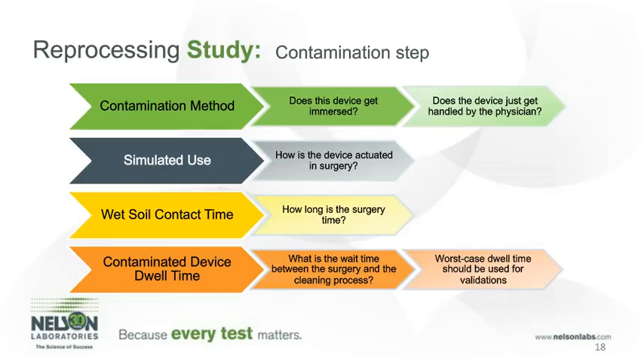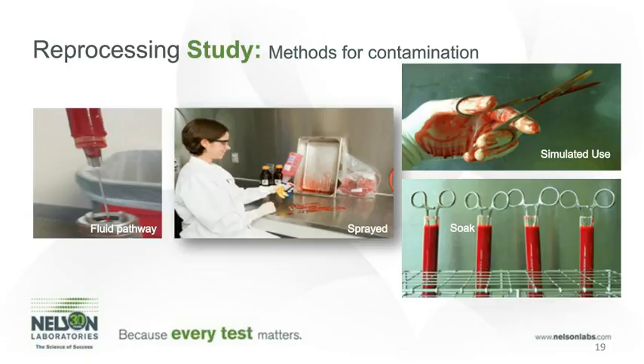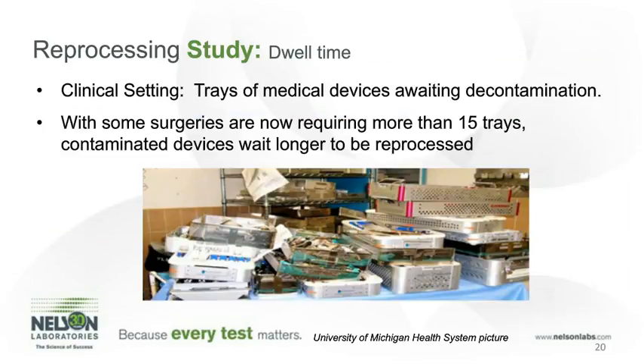Here are some examples of how the contamination takes place. We can either fill the fluid pathway with a blood soil, spray the soil on, handle the device with bloody gloves, or soak the device, or use a combination of these depending on how the device is utilized. Here is an example of what we do not want to see in the clinical setting. As we know, some surgical centers sometimes get backed up with many trays, and there are some surgeries now requiring more than 15 trays, and there sometimes may be longer wait times for these to be reprocessed. The central processing area can get very overwhelmed with the number of devices they need to reprocess, and so we need to ensure that the cleaning instructions for these devices are easy to follow and maintain throughout the area.